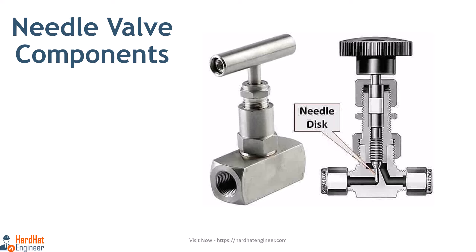Fluid flowing through the valve turns 90 degrees and passes through an orifice. Due to the needle shape of the disc, a certain portion of the disc will pass through the seat opening before the disc comes in contact with the seat, which has to match the tapered design of the disc. This arrangement permits a very gradual increase or decrease in the size of the opening. All field analog instruments are fitted with a needle valve to control flow entry, where sudden surges of fluid under pressure can damage the instruments.